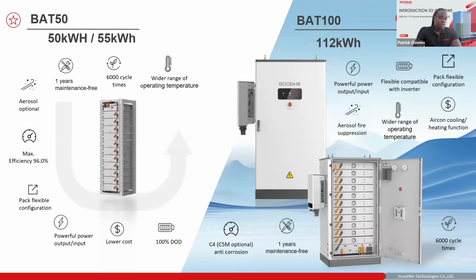Both batteries have 1 year maintenance free. We can do pack level fire extinguishing using the aerosol. Flexible installation, they're low cost, portable, 100% depth of discharge, and up to 6,000 cycles of usage. So both options. Now, you can see also in the BAT100, you have an option of installing your battery on the side of the panel. Now with the BAT50, you can do 6 pieces of the battery to one inverter. So that gives you 300 kilowatt hour. With 300 kilowatt hour, if you're doing the maximum, you'll be doing almost 3 megawatt hour with indoor batteries. And with the BAT100, you'll be doing 4 in one inverter, so you can achieve up to 4 megawatt hour, over 4 megawatt hour if you're doing the maximum 10 pieces of inverters. So those are the batteries that we have.